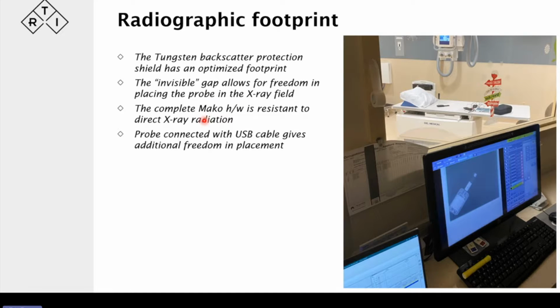And this also again shows you that the design is such that the electronics itself in the hardware is resistant to direct X-ray radiation. Now, if you have some other applications where you want to have a smaller footprint, or from other setup reasons, we may disconnect here and have a cabled connection instead between the probe, which is there, and the base unit, so you can have the base unit outside the field and have less of an impact on the measurement. So that's what it looks like. I thought it was quite an interesting picture. Thank you, Cam.